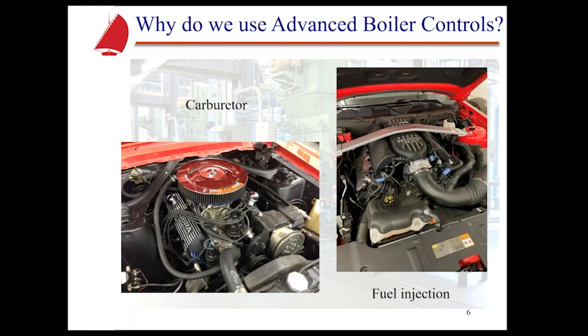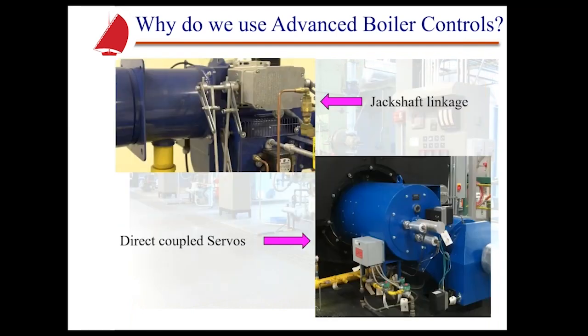So if we're talking about advanced boiler controls and we're talking about parallel positioning, it truly is like going from a carburetor to fuel injection. It just makes a huge difference in how we can control that combustion process. The jack shaft linkage, it is complicated. There's no doubt about it. And a lot of people, quite honestly, it takes a while for them to learn how to set this up properly. Whereas with direct coupled servos that are coupled directly to the combustion air damper, where we also have a servo directly coupled to something like a gas butterfly valve, we can control those much, much closer and much more precisely.